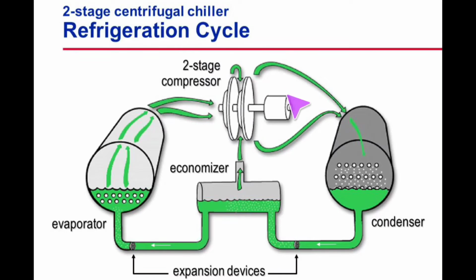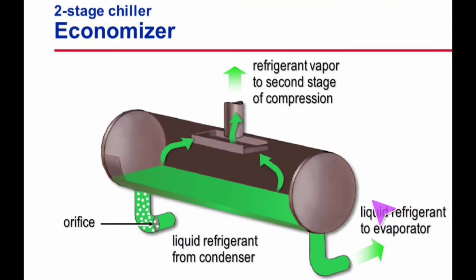And this, again, is all a CVHF design. CVHE does have a little bit different design. We will also go deeper into the additional components of this system, because all that's part of this cycle. Right now, we're heavily discussing just the refrigerant section itself, the main nuts and bolts of what makes the machine operate. So here's a little bit deeper view of the CVHF economizer specifically, or also a two-stage chiller economizer.